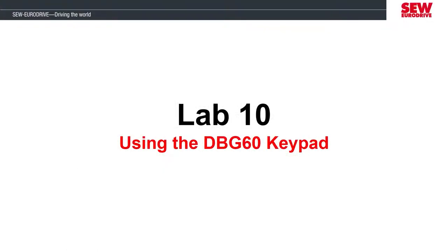Hello everyone, welcome to lab 10. In this lab we will switch to using the handheld keypad, which is an optional accessory to the MOVIDRIVE instead of the Motion Studio software. Sometimes it's not convenient to open software just to monitor a parameter or reset a fault. The keypad has the ability to view and change many different parameters, view the fault history, and reset faults. If your MOVIDRIVE is installed within visual sight of the application, you could also operate the motor manually using the keypad if it's safe to do so.